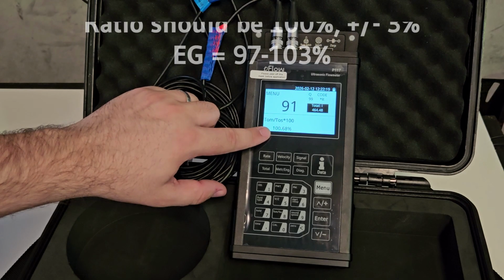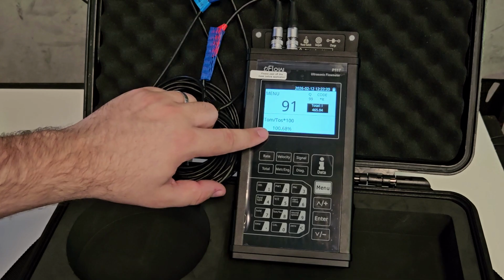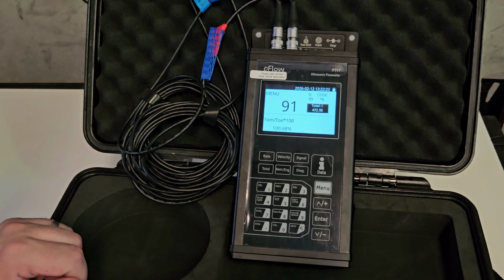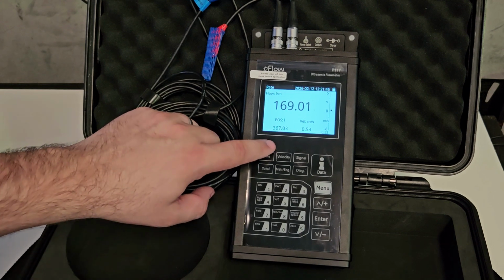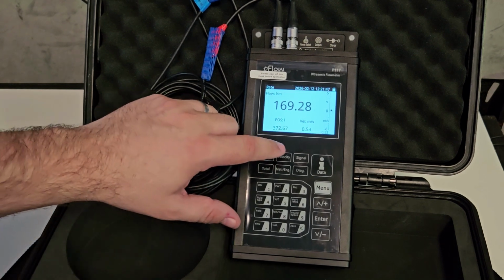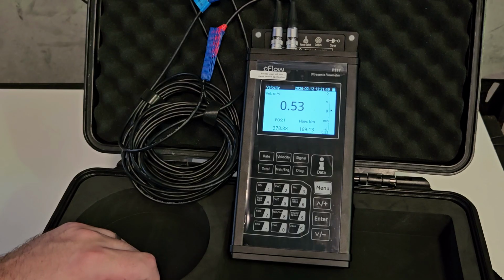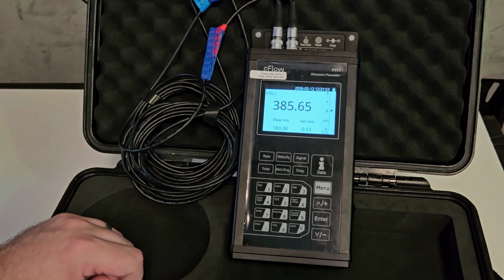If either of these two checks are out of range, it can indicate a problem with the application or installation. Please recheck parameters and installation, or check through the installation guide and manual to troubleshoot. Maybe there is a parameter incorrectly set or a problem like not enough straight pipe length causing turbulence in the flow, aeration, or too much solids in the flow. Now you can press the rate shortcut to display the flow rate. You can press the velocity shortcut to show velocity. Or you can press the total shortcut to show the flow totalizer.